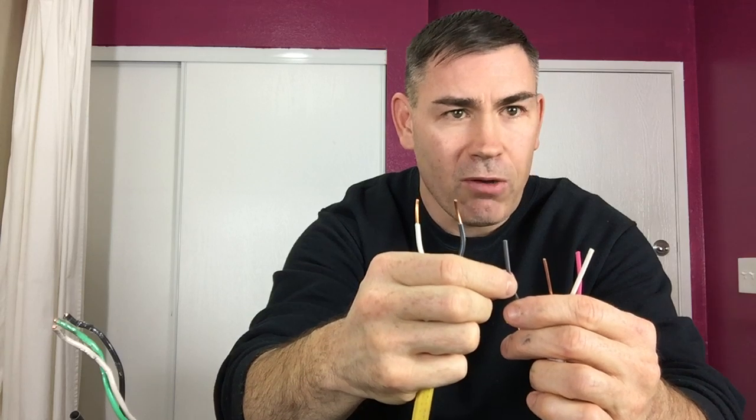Now, the 14, again, like I said, refers to the thickness of the wire. This here is called 12-2. Again, the 2 because there's only 2 insulated conductors and the ground. But they call this 12-2 because 12 refers to the size, just as 14 refers to the size. Now, I don't know if you can tell on here, but it works inversely, numerically. 14 is a larger number than 12 in the real world, yes. But here, 14 is smaller in thickness than 12. So the lower the number, the thicker the copper wiring, meaning the more electricity that can flow through it.